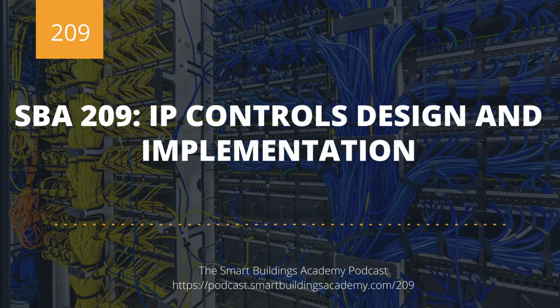The best way to describe IP controls is to think back to a couple years ago when most manufacturers started to come out with IP-enabled plant controllers. So they came out with these controllers that were a combination of supervisory device and field controller. They had the input and output capability of a field controller. They had the programmable logic of a field controller, but at the same time, they had an IP connection to the greater IT network. And they also had a lot of supervisory functionality.